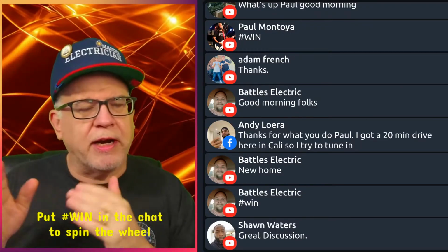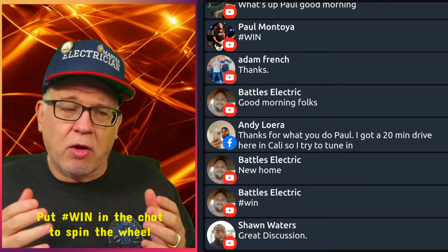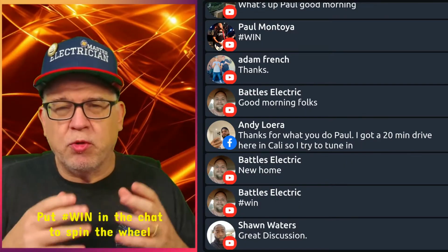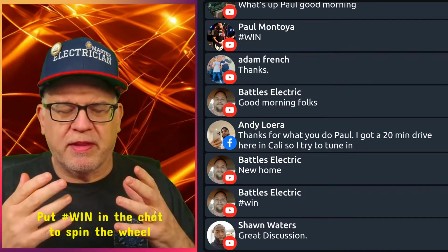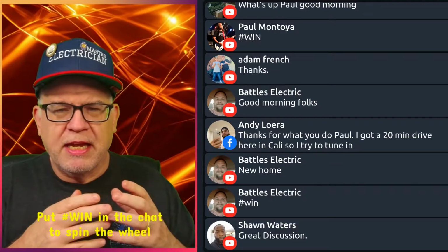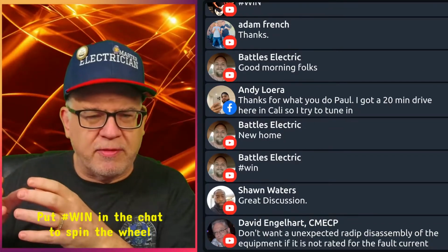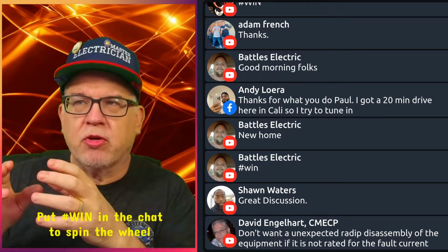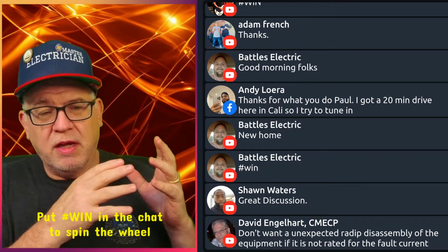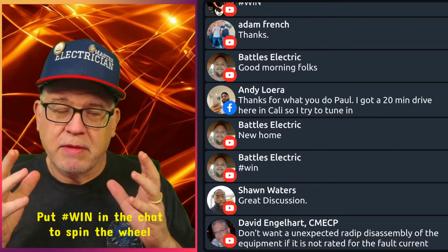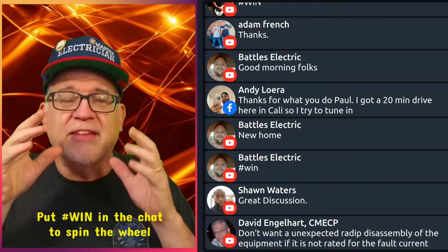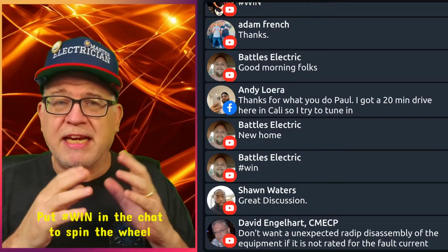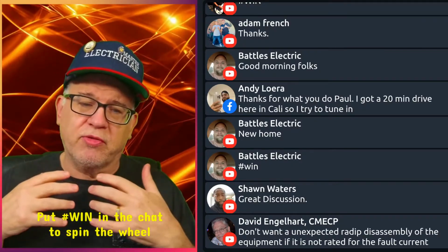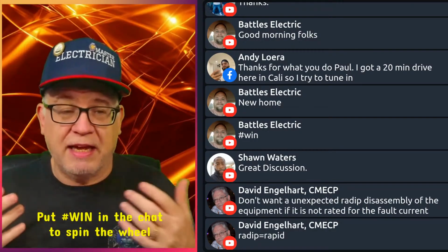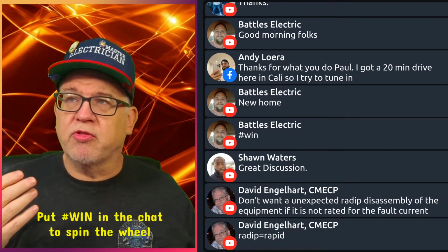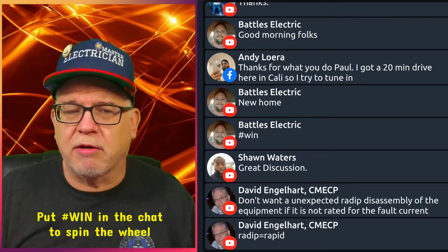If you're doing it in other areas of the code, it's less impactful for you if you have service equipment that is well within the scope of the AIC or the SCCR of whatever is being supplied by the utility. Then you go further down with feeders into the system. If it's 25,000 at the source and the service equipment is rated 35,000, then going downstream in a feeder it's going to be less than at the source, inherently, because the impedance of the conductors as it moves downstream is going to reduce it. There are certain areas in the code that are still going to require you to do a calculation on that.